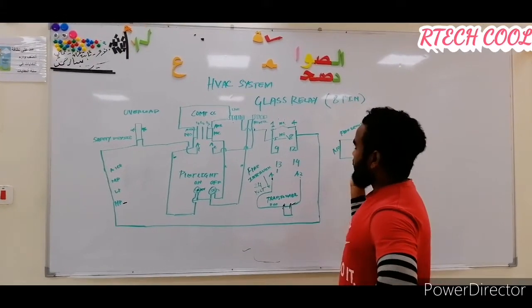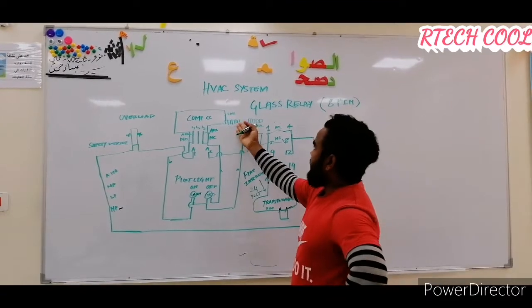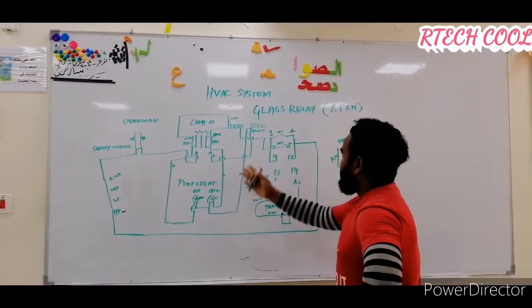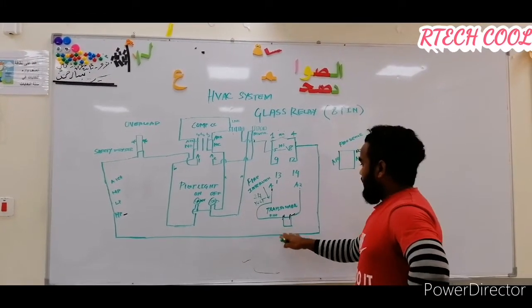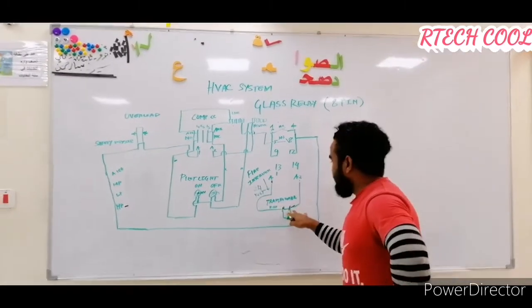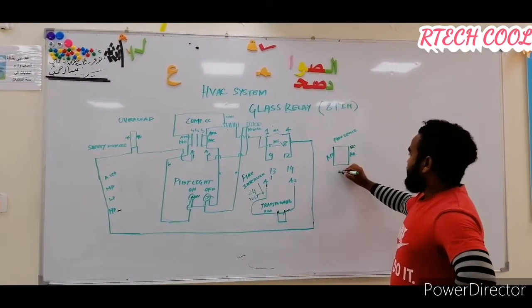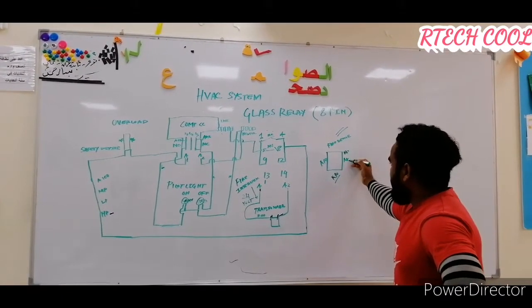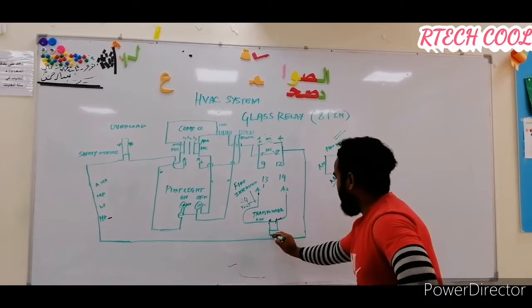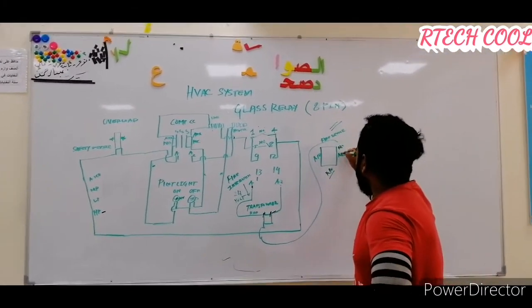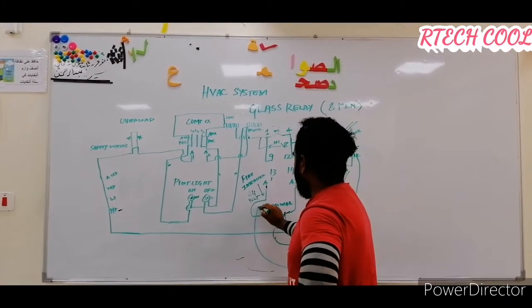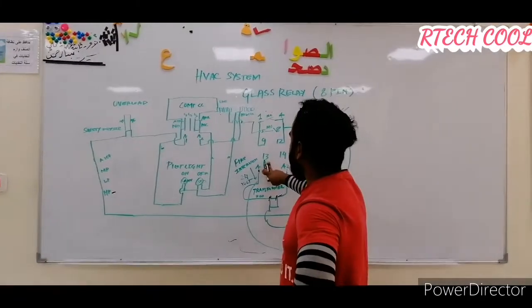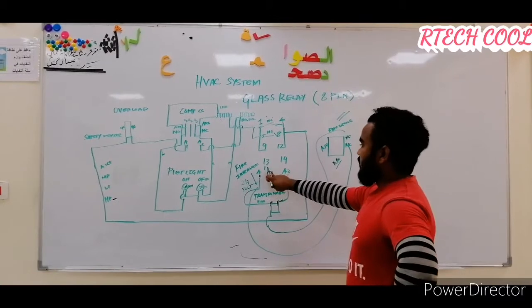If we turn the isolator on — power on — our line and neutral voltage will activate and supply power to the transformer. The transformer supplies 24V, and the 24V comes to the NC point. If there is no fire, everything is normal, so the NC point stays closed. The current will come back here and go directly to A1, which is point 13 — the coil voltage phase.